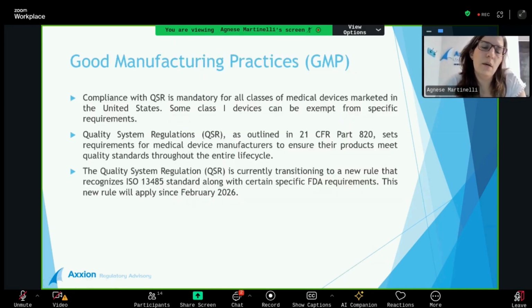If we talk a little about the good manufacturing practices that must be implemented by all medical device manufacturers, compliance with the QSR is mandatory for all classes. There might be some exceptions in class 1 devices, but in general it's all mandatory. It is outlined in 21 CFR part 820, and it sets the requirements for all manufacturers to ensure that their products meet the quality standards through their entire life cycle.